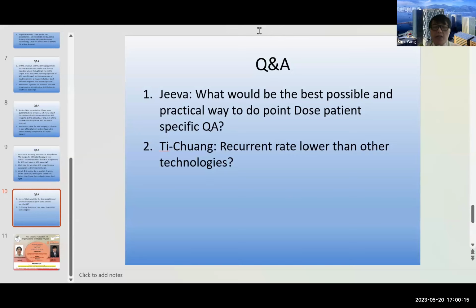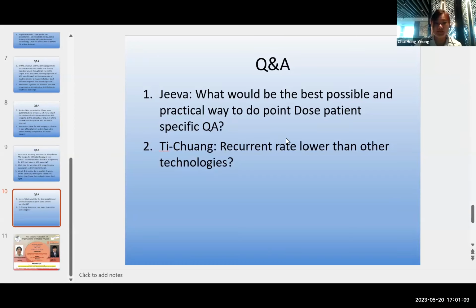If the audience asks how we perform the point dose patient specific QA in the pre-treatment QA, currently our QA system uses the ArcCheck. For the ArcCheck we have a dedicated QA platform, and we place the ArcCheck on the platform. The whole system is rigidly set up, and then we insert a farmer chamber in the center of the ArcCheck and deliver the patient specific QA just as on the conventional linac. So we measure the point dose and dose distribution using the ArcCheck. Yeah, thank you. I think we need to have another hands-on workshop, Dr. Kimi, to show examples of those calculations.